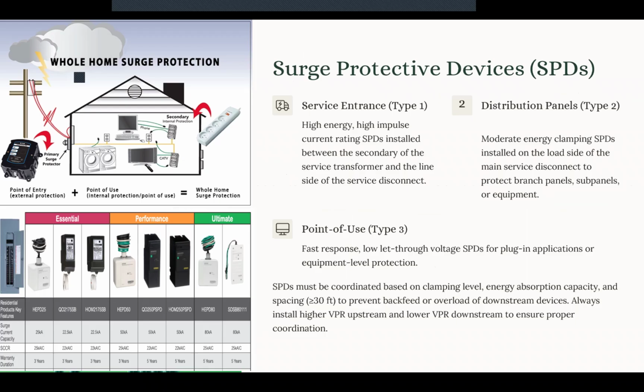Now, we also mentioned that these systems should have surge protective devices, which are voltage clamping or diverting devices that are designed to protect the sensitive devices from transient overvoltages. Those overvoltages can be caused by lightning strikes or switching surges or inductive kickbacks. It is important because even a microsecond level transient can cause a logic error or data corruption or permanent damage in the component.